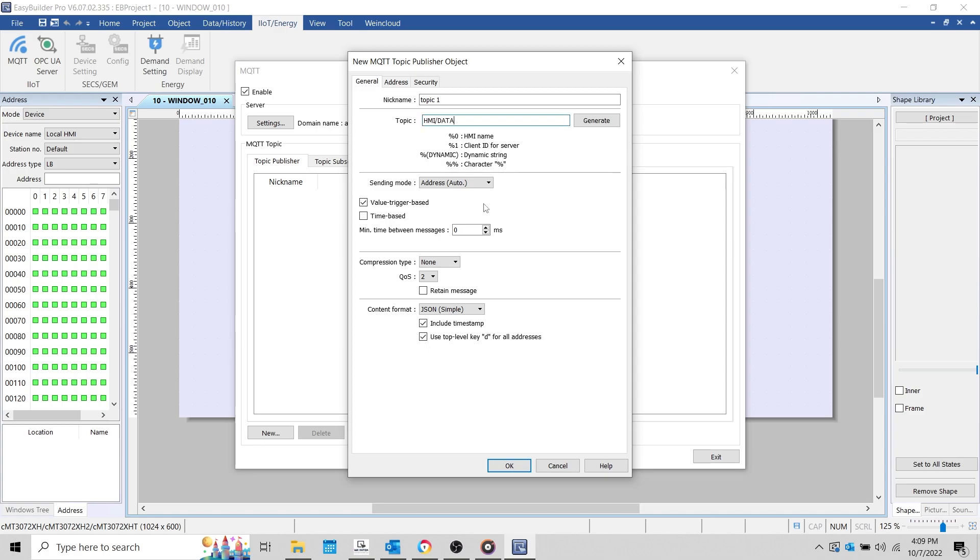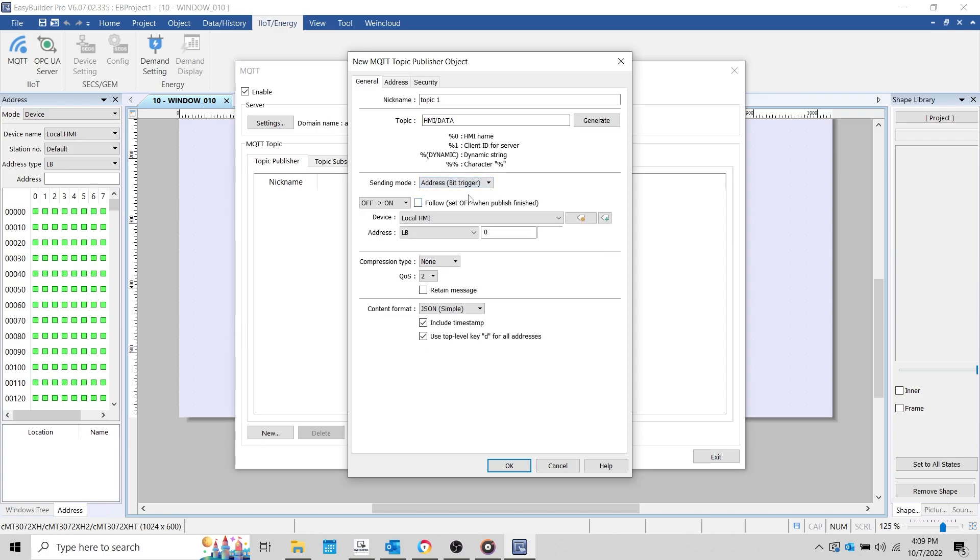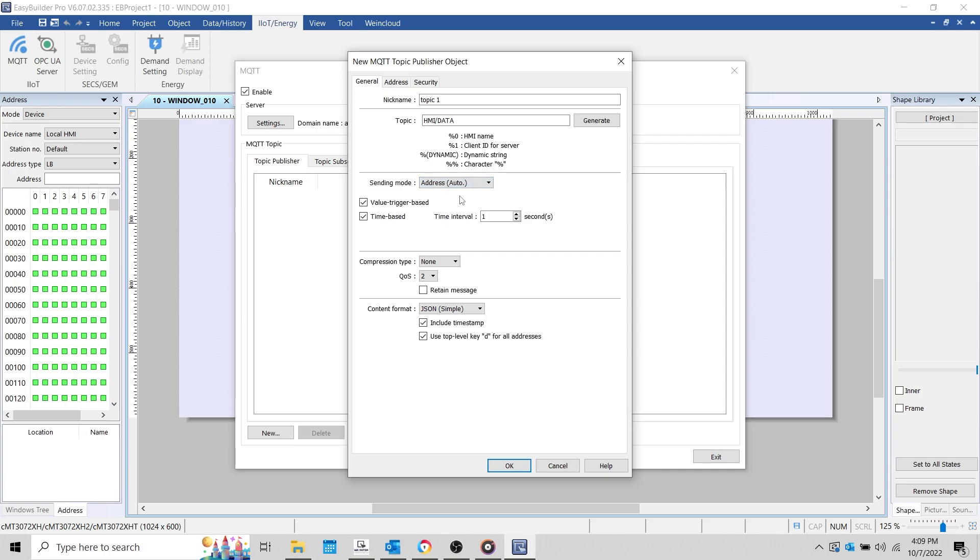There are a few different triggers that can be used when publishing data. We can have the HMI publish to the broker when the value changes. We can also publish on a preset time interval, or even publish when a Boolean trigger changes states, or when an alarm is triggered within our project. During this demonstration, we'll send messages on a preset time interval. I don't need to configure a compression type, but you may do so if required by your application.